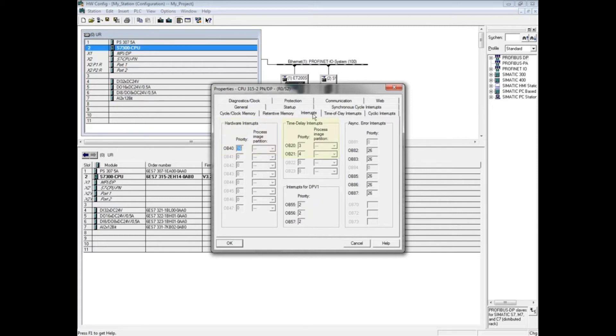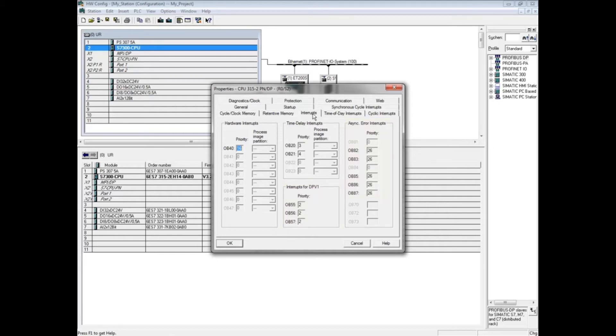The interrupts include master-slave Profibus DPV1, cyclic data exchange interrupts, and asynchronous hardware-related error interrupts. If several organization blocks are called at the same time, the priority number determines the execution order. The higher the number, the earlier the block runs.